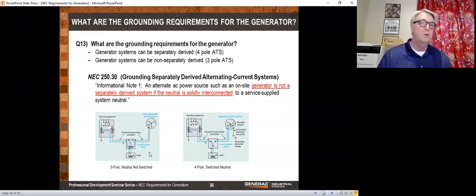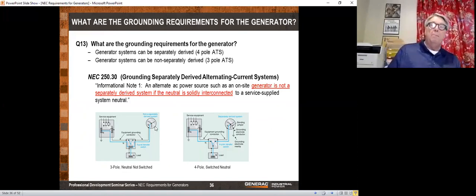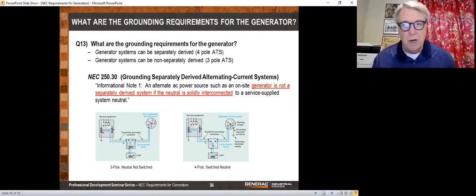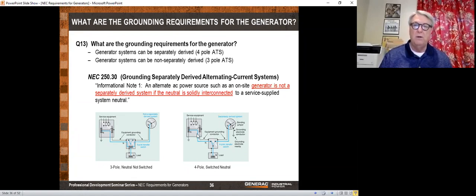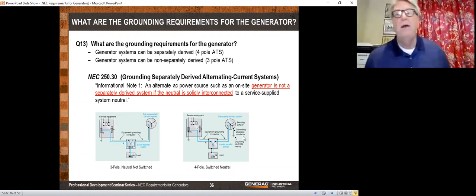Now, the generator enclosure still has to be grounded. You still have to have a ground wire in there, but you do not have that bond between the neutral and ground at the generator. That is at the service. And if you put another one in at the generator, then you have 2 neutral to ground bonds, and that's a code violation. So if you have a 4-pole transfer switch, then the neutral is switched. And because it's switched, then that neutral can never be connected to both the service entrance ground and the generator ground. So in that case, you're going to have 1 neutral to ground bond at the service and a second neutral to ground bond at the generator.